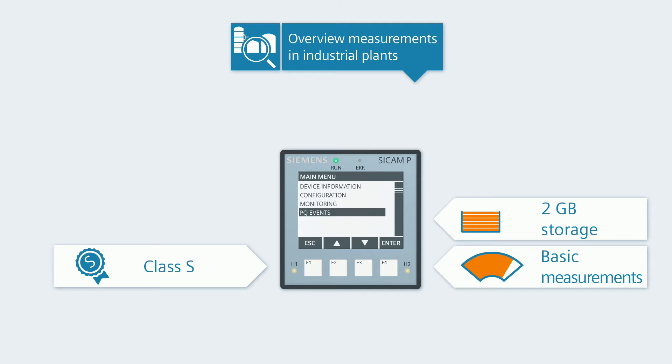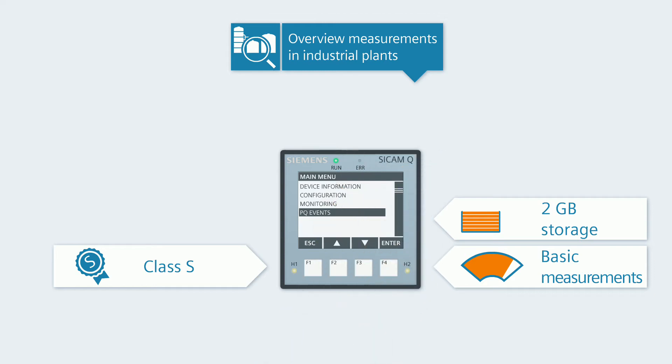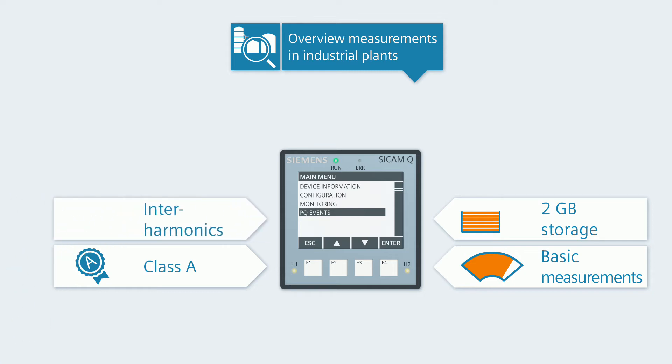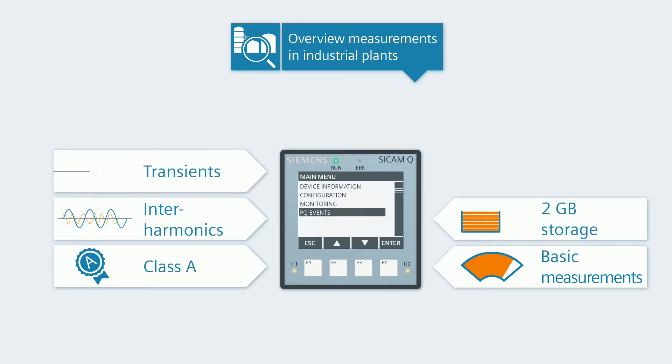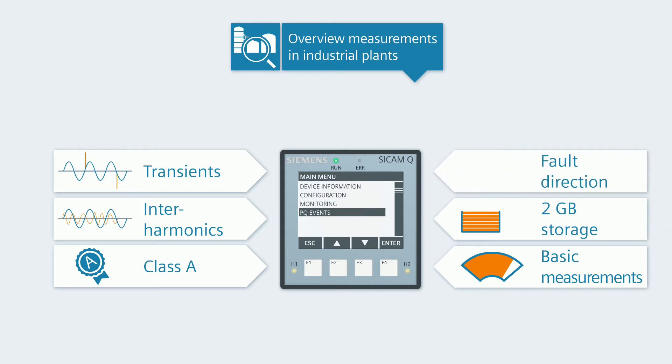At first glance, SICAM Q100 only differs from the SICAM P855 through its type designation. But this Class A measuring device not only has a higher accuracy than the SICAM P855, it also acquires interharmonics and transients. SICAM Q100 even identifies whether a fault comes from the energy producer or from the energy consumer.